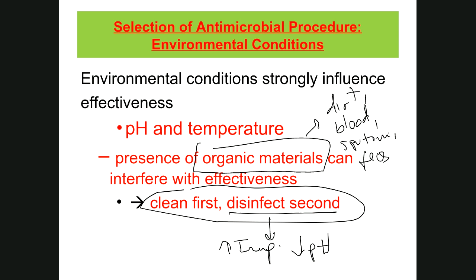Most chemicals are more effective at higher temperatures and lower pH. For example, household bleach can kill a suspension of Mycobacterium tuberculosis at 55 degrees centigrade in half the time as at 50 degrees. So after disinfection, or while disinfecting, raise the temperature and lower the pH if you can use a warm disinfectant - that can make all the difference.